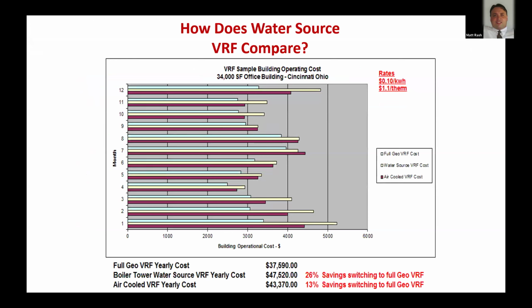These are some comparisons for how these water source VRF systems compare versus air source. This is a typical model that was done for a Cincinnati 34,000 square foot office building. You can see full geo operating costs being the lowest at around 37,000. This was based on 10 cents a kilowatt hour and $1.10 a therm. If you were to do this with a full boiler tower type design, it was up closer to 47,000. And if it was air cooled VRF, traditional VRF, it was 43. So this largest operating cost with boiler tower is coming mostly from the heat of absorption, because that's all coming from the boiler that's present on the project, versus geothermal, where you're sourcing that heat from the ground. So it really is your optimal system.